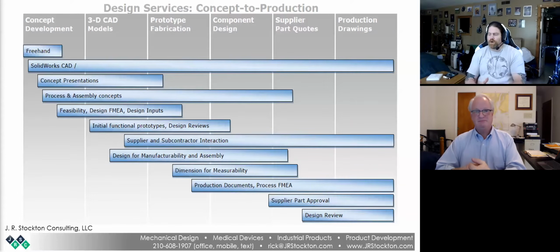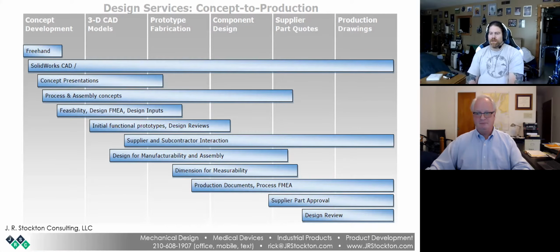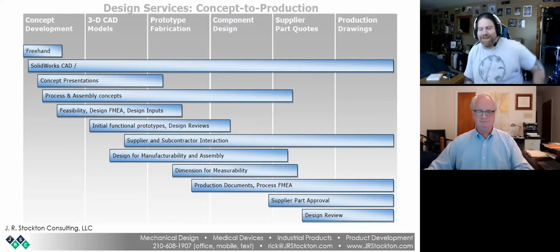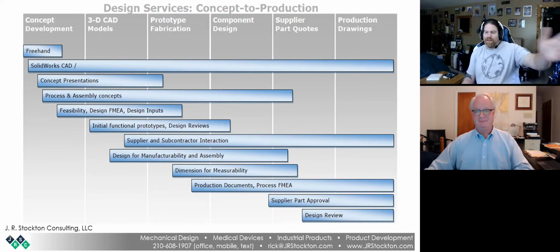Okay. So as an auditor, one of the things in there is you have to define the training requirements. Be careful if you're going to have a cross-functional team where not everybody in the room is trained on risk management. Don't write your risk management procedure to say everybody that participates in a design FMEA has to be trained according to ISO 14971 and go take this course at, I'll just pick on AAMI because we do some trainings for them, so you have to go take Rob Packard's class at AAMI on this topic. Don't write your procedures that prescriptive.